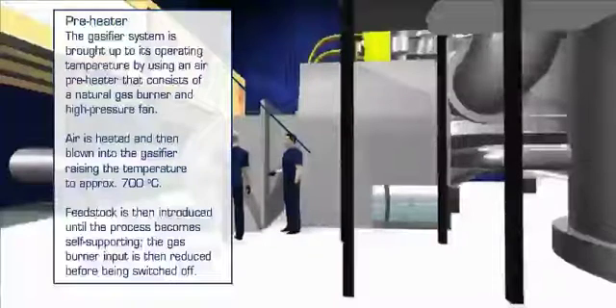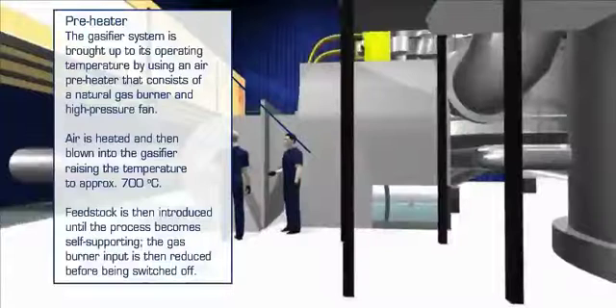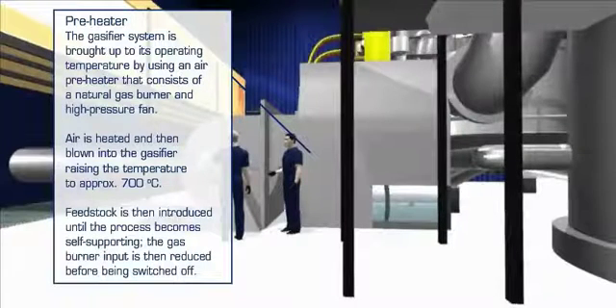Air is heated by the gas burner and blown into the base of the gasifier, raising its temperature to approximately 700 degrees Celsius. At this point, the feedstock is gradually introduced until the process becomes self-supporting. The gas burner input is then reduced before being finally switched off.